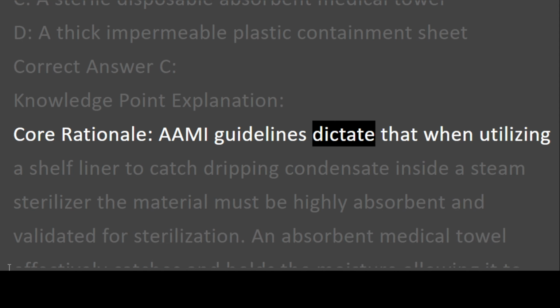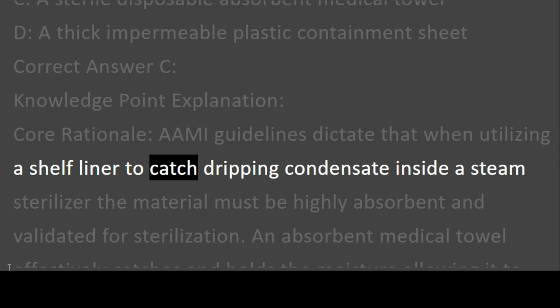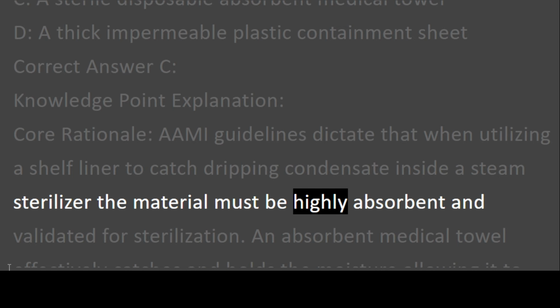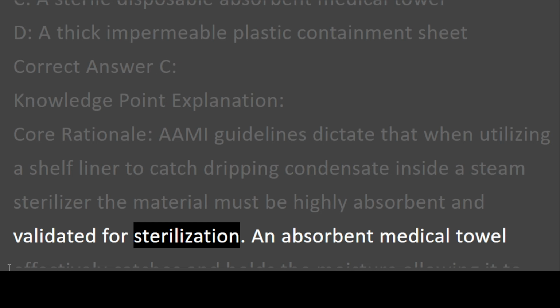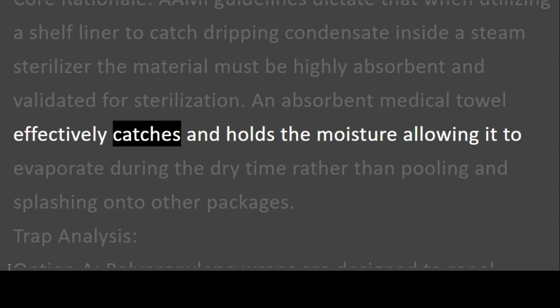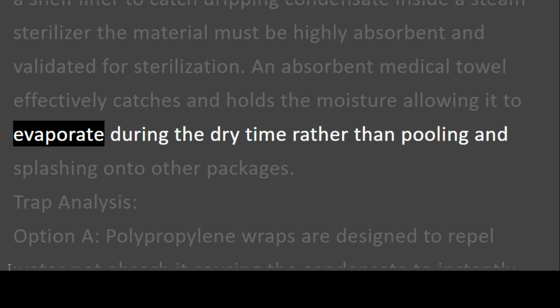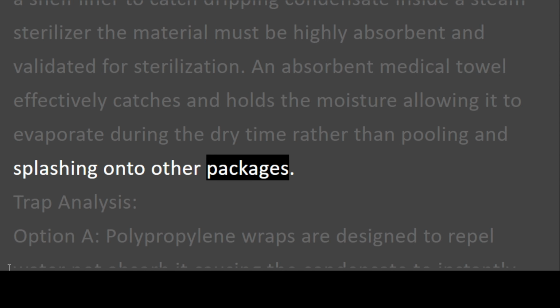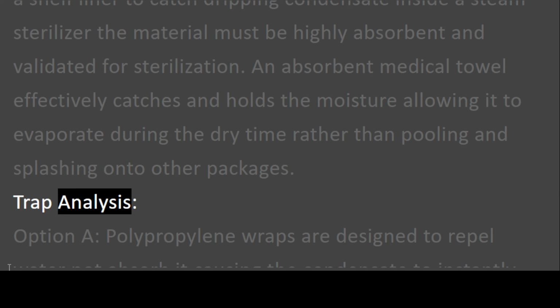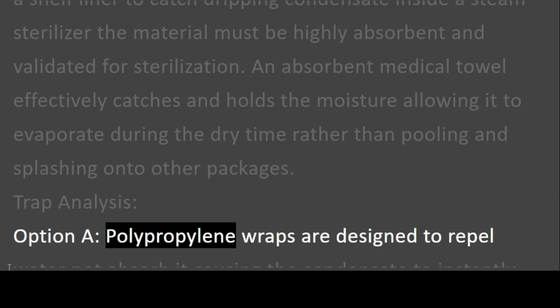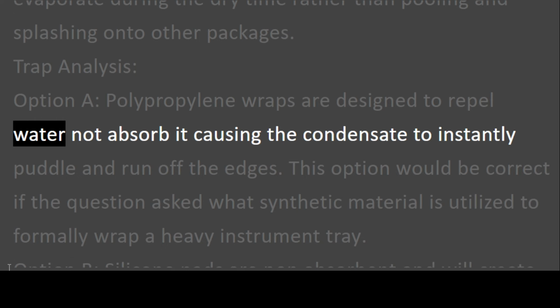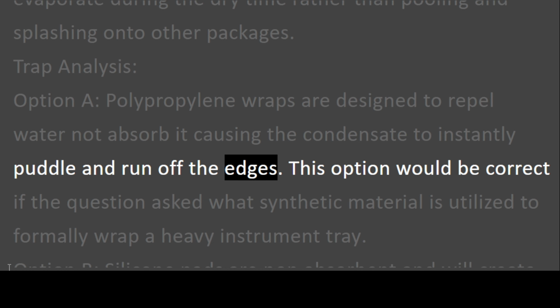AAMI guidelines dictate that when utilizing a shelf liner to catch dripping condensate inside a steam sterilizer, the material must be highly absorbent and validated for sterilization. An absorbent medical towel effectively catches and holds the moisture, allowing it to evaporate during the dry time rather than pooling and splashing onto other packages. Trap analysis. Option A. Polypropylene wraps are designed to repel water, not absorb it, causing the condensate to instantly puddle and run off the edges.